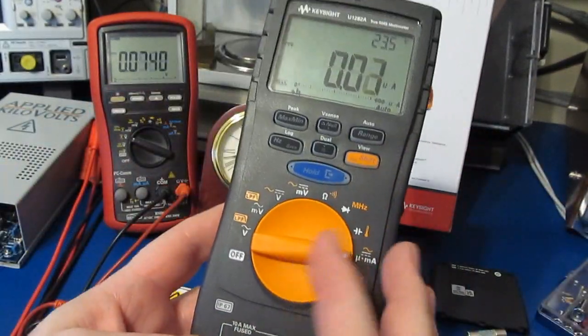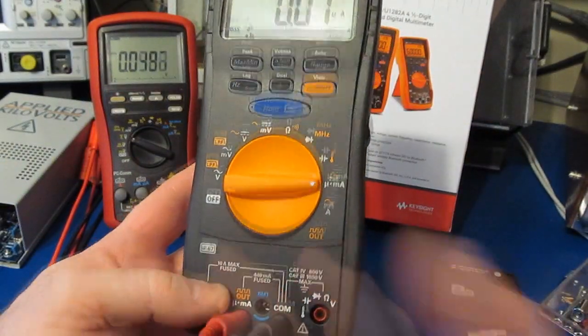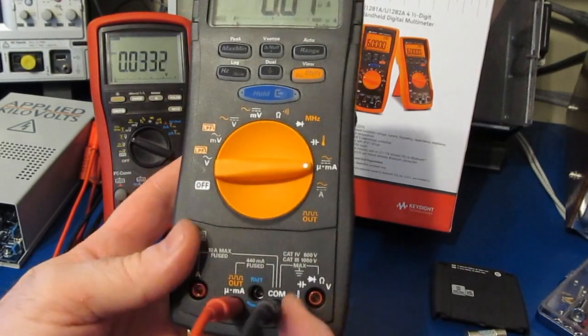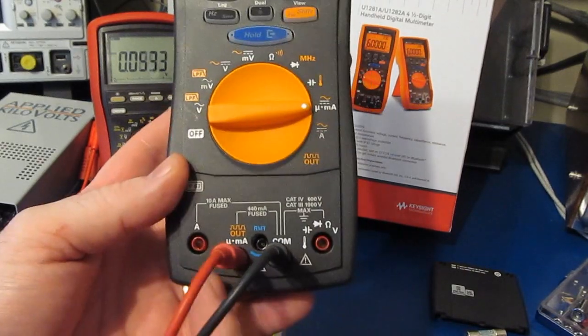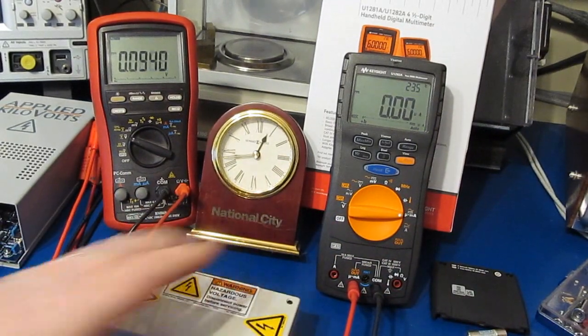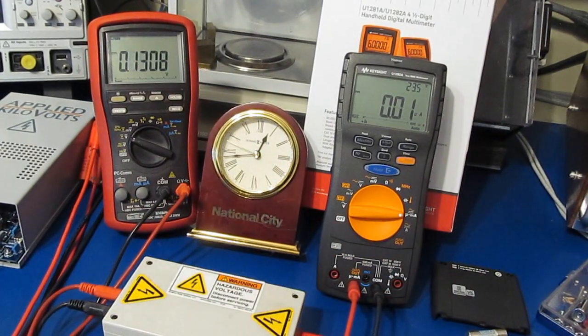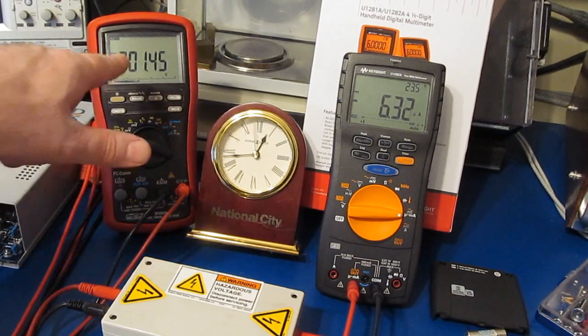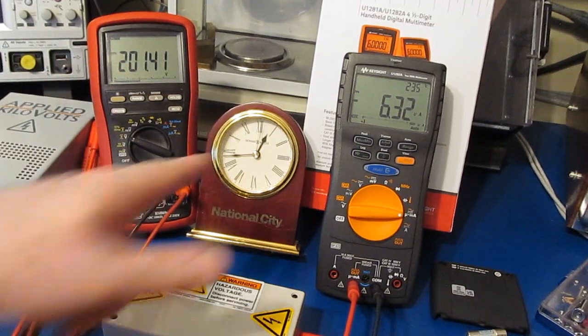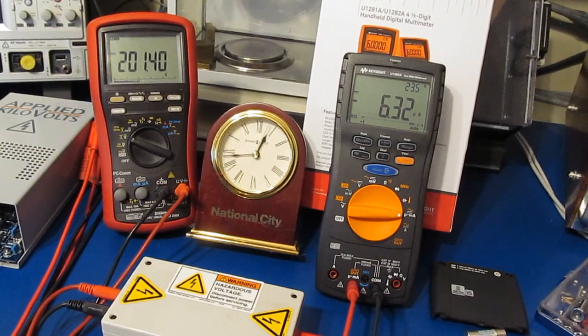Again, this particular meter is rated for 1000 volts. So we're going to be applying 2000 volts between the common and then the two current inputs. And we'll apply that voltage for 1 minute. Alright, so let's just go ahead and we'll turn up the voltage. And here we have it, so roughly 2000 volts. And let's just wait for a minute and see if anything happens.